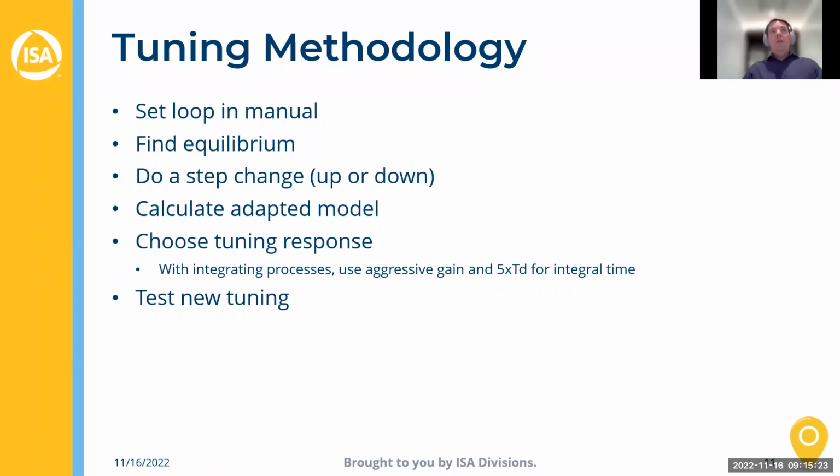So to do a tuning, yes, Bob. I guess my point was that's something people need to pay attention to, because the entire tuning process changes if your ramp time changes. I agree. Yeah. So you don't need to remove it, but don't change it afterwards, of course, because you're right, it will change your response. Same thing with the filtering. So use your filtering first, then you can do those tests, because they're part of the process, a bit similar.